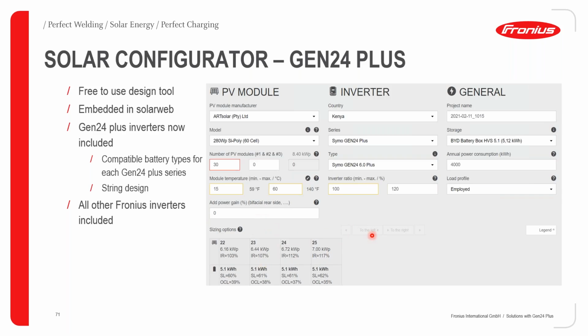We highly recommend the solar configurator, regardless of which other configuration tools you're using, because it allows you to optimize your string design for all Fronius inverters. The string design is affected by things like minimum and maximum temperatures, and the maximum and minimum inverter ratios you'd like to use. So using the solar configurator is something we highly recommend to ensure your string design, as far as lengths are concerned, is optimized.